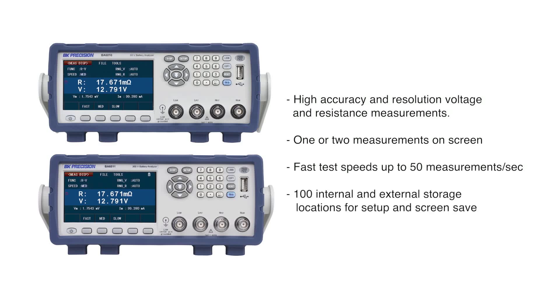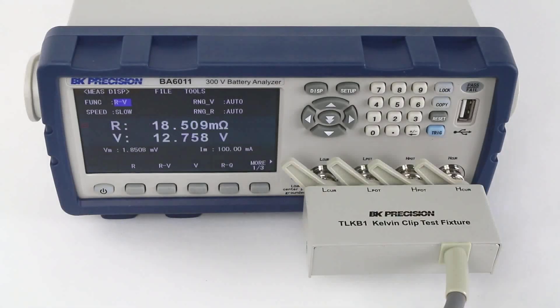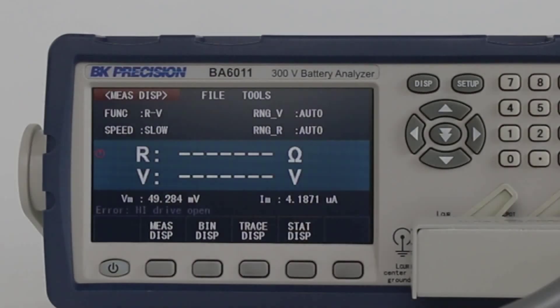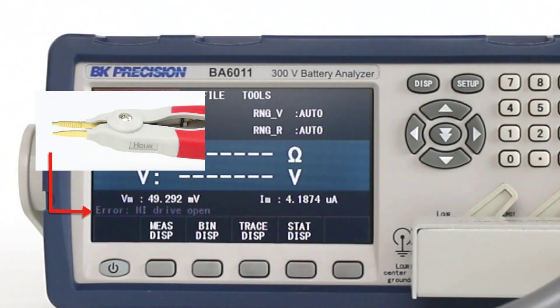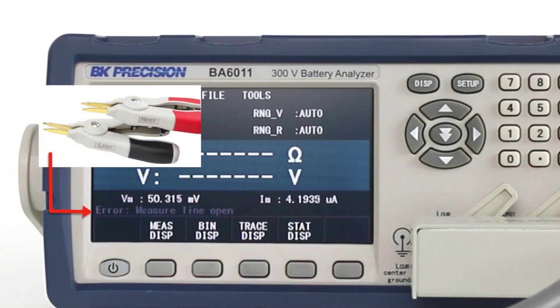All other features are identical and include high accuracy and resolution voltage and resistance measurements, one or two measurements on screen, fast test speeds up to 50 measurements per second, and 100 internal and external storage locations for setup and screen save. The four terminals on the front of the unit are used together with the Kelvin Clip test fixture, which helps minimize the influence of test lead resistance while improving measurement accuracy. The on-screen probe monitoring system detects test probe contact failure and damaged leads to ensure reliable connection and measurements.